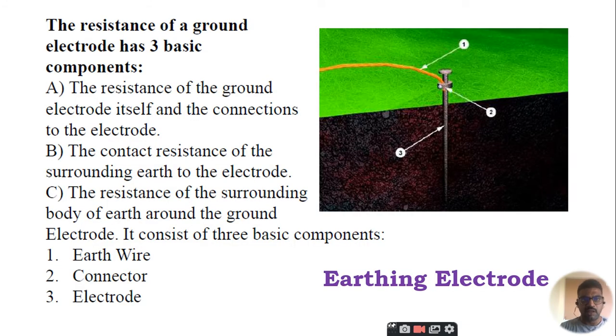The resistance of the ground electrode has three basic components in case of an earthing electrode or earthing rod. The first is the resistance of the ground electrode itself and the connections of the electrode, the contact resistance of the surrounding earth of the electrode, and the resistance of the surrounding body of earth around the ground electrode. The first one is known as the earth wire, which is important and is connected with each and every socket where the earthing is provided. Then we have the connector. It connects that wire with the earthing rod, and the final element is the earthing rod, which is to be buried inside the earth or ground.